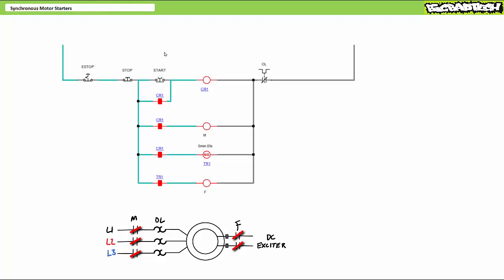As we anticipated, the motor starts in induction mode using the amortisseur windings in the rotor, and after a predetermined delay allowing a degree of acceleration, the field contactor closes and energizes the rotor field, which locks into the stator's rotating magnetic field, suitable for constant speed operation characteristic of a synchronous motor. Here's the system in operation once again.